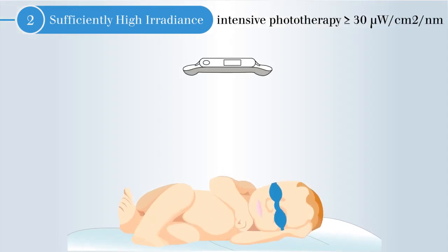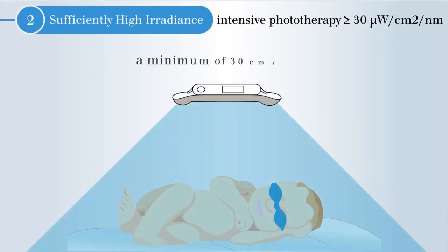The second consideration is sufficiently high irradiance. This is the power per area of light received by the neonate. To ensure maximum irradiance, the distance between the patient and light should be minimized.